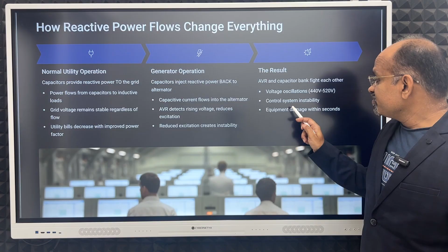Then the result: the AVR and capacitor bank fight each other. One increases the voltage, the other decreases it, then it increases again—they keep fighting each other. Voltage oscillates between 440 and 520, increasing and decreasing repeatedly, leading to control system instability, where the control system gets confused about what's happening as voltage levels go up and down.